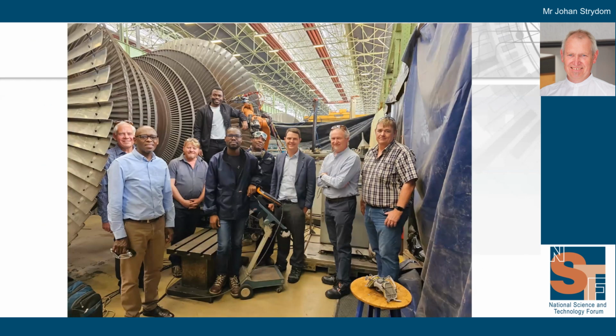Here's an example of work we're doing at the moment with Eskom Rotec, the engineering arm of Eskom. We do maintenance on these big gas turbines, and in the photo, if you look at the second ring of blades, you'll see it's got a ring there that keeps the blades in position. One of the things done when the rotor is taken out for maintenance is those rings are inspected, and from time to time there are cracks in them.